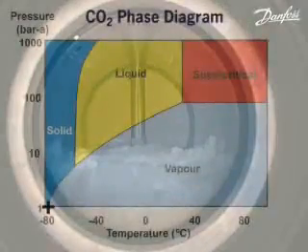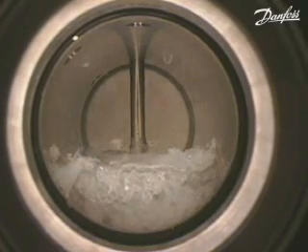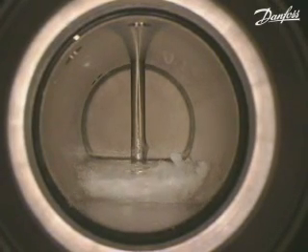Solid CO2 is also known as dry ice. It has a surface temperature of minus 78.4 degrees C at standard atmospheric pressure. The pressure inside the cell is now approximately equal to the surrounding atmosphere of 1 bar absolute. The vent valve is closed. The entire cell is now below ambient temperature and will absorb heat from the surroundings. Triple point conditions are re-established as the solid CO2 melts, and as the pressure and temperature rises, the cell contains liquid CO2 and vapour in equilibrium.